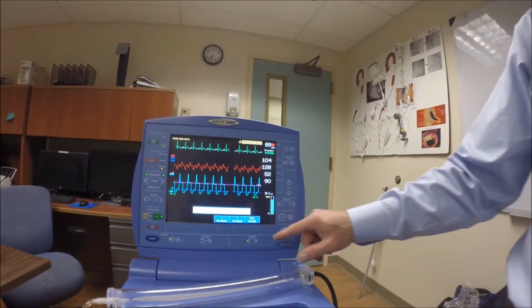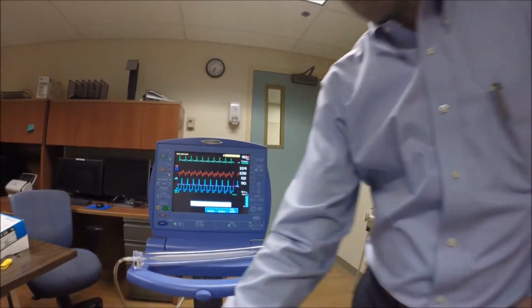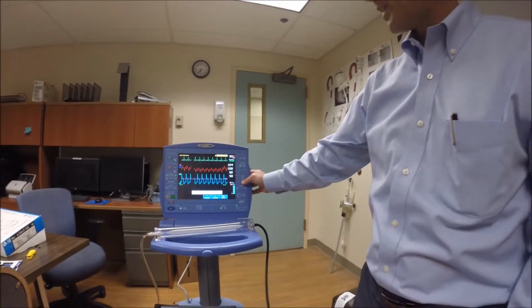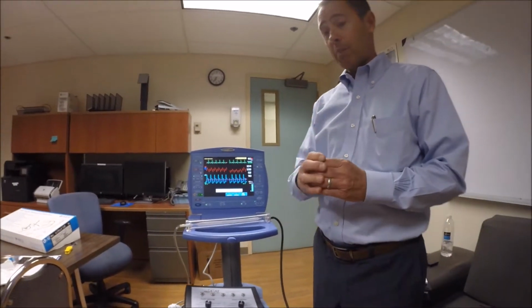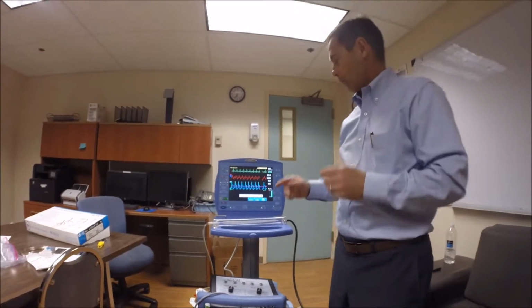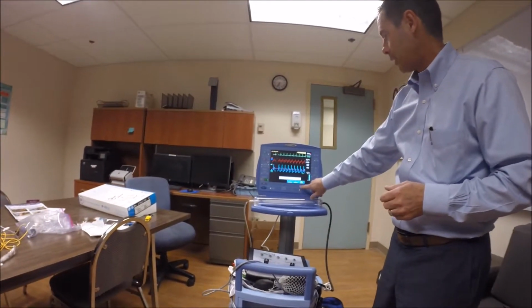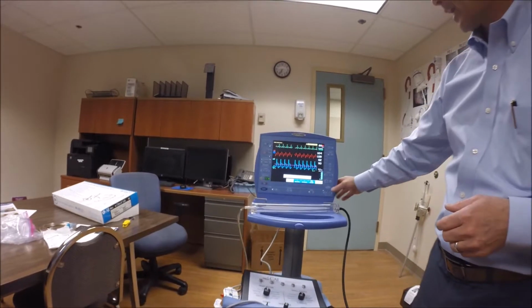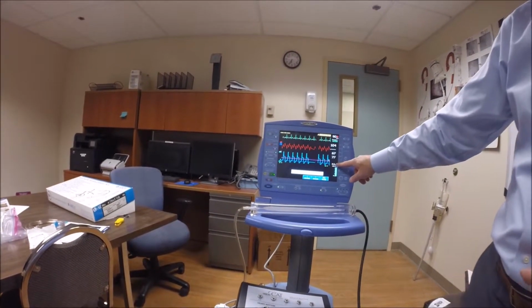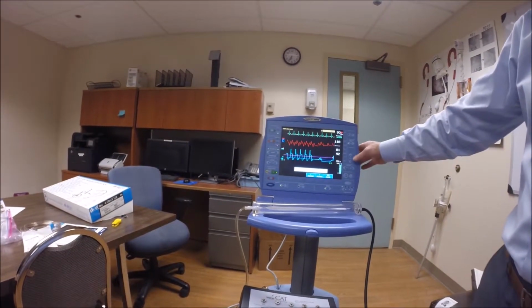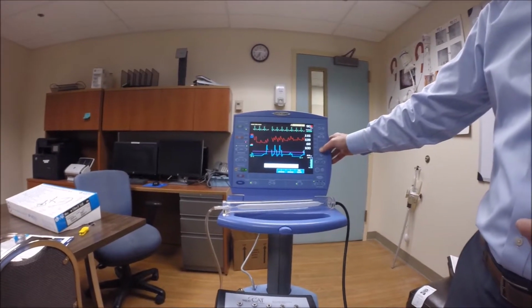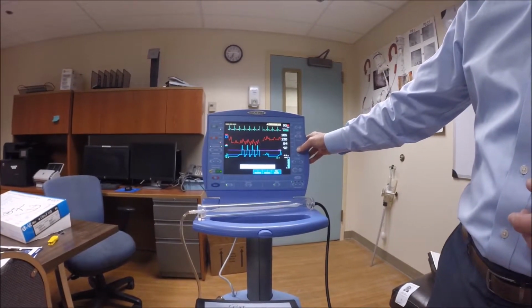New pressure readings. Tomorrow, when the patient's in ICU, that cursor may be down in here, which means my balloon is not big enough now. And so I can go to balloon volume and jump it up to full volume and hit the apply button and bring it up from 36.5 right back up to 40, and then bring my cursor back to that new plateau pressure. All right?